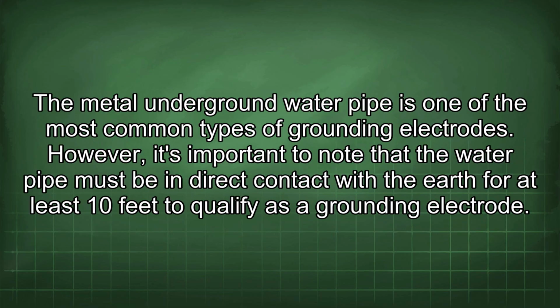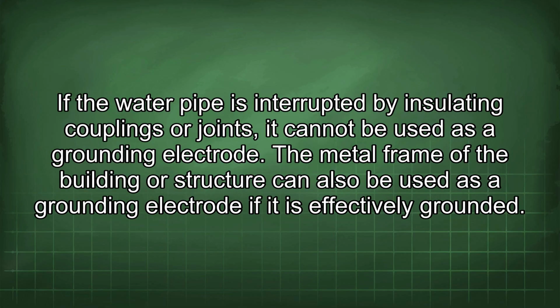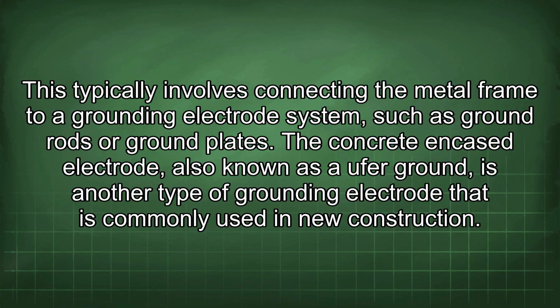The metal underground water pipe is one of the most common types of grounding electrodes. However, it's important to note that the water pipe must be in direct contact with the earth for at least 10 feet to qualify as a grounding electrode. If the water pipe is interrupted by insulating couplings or joints, it cannot be used as a grounding electrode. The metal frame of the building or structure can also be used as a grounding electrode if it is effectively grounded. This typically involves connecting the metal frame to a grounding electrode system such as ground rods or ground plates.